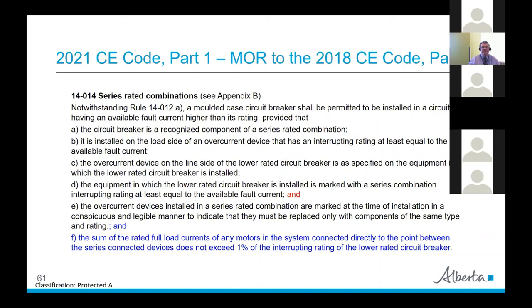On series rated combinations, item (f) has been added: the sum of the rated full load currents of any motors in the system connected directly to the point between the series connected devices shall not exceed one percent of the interrupting rating of the lower rated circuit breaker. This makes allowance for the motor contribution to any fault in series rated combinations.